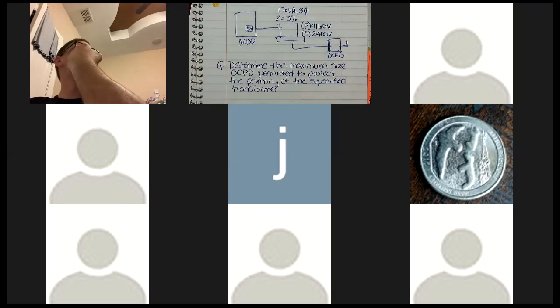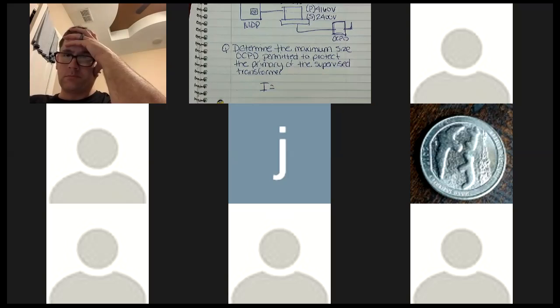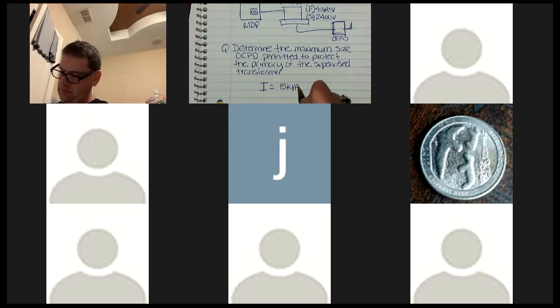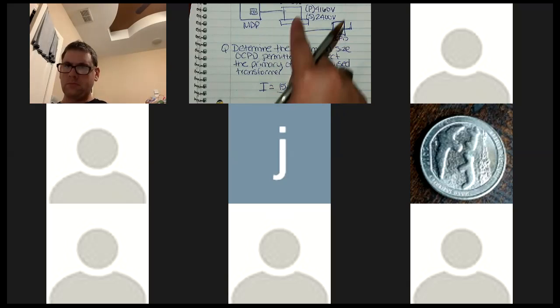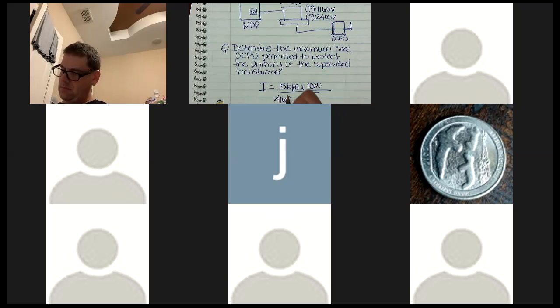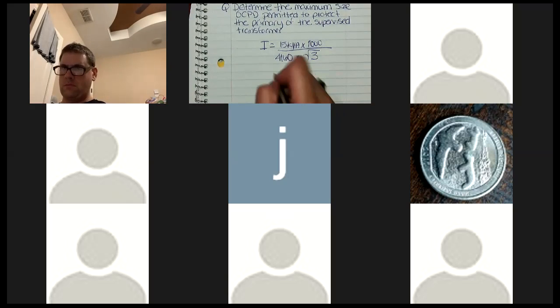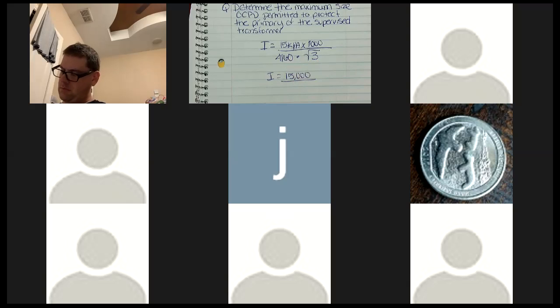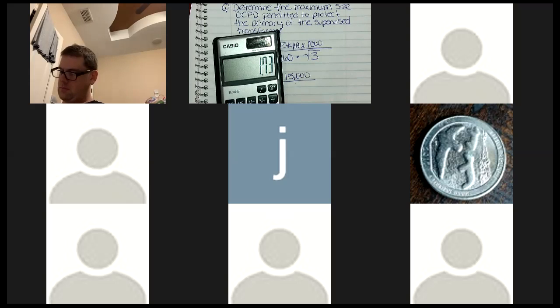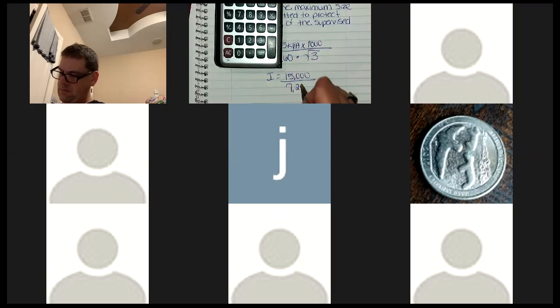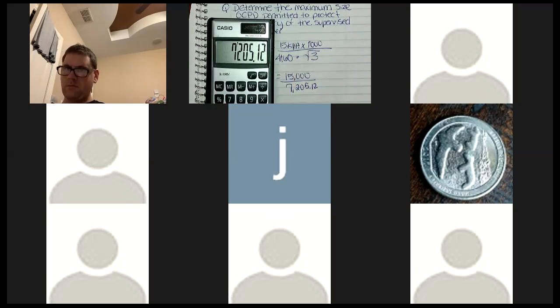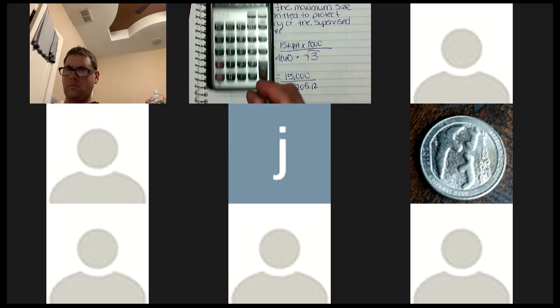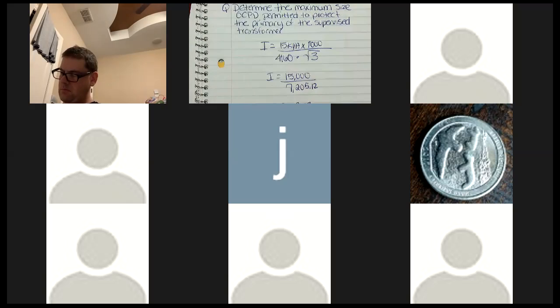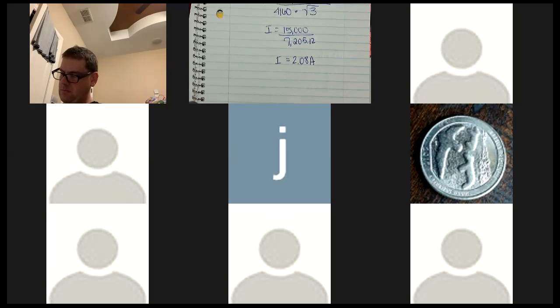Okay. So right here, I know that I'm going to have to figure out amperage. So here I go. It's 15 kVA, times 1,000. It's 3-phase, and my voltage on my primary side is 4160, right? That's what I got. So then I come over here. This is 15,000. Let's see, 4160 times 1.732, 7,205, whatever. That's what I get, right? So 15,000 divided by 7205.12, I get my amperage is 2.08. I'm just going to round it off right there. Amps. That's where I'm going to stop.